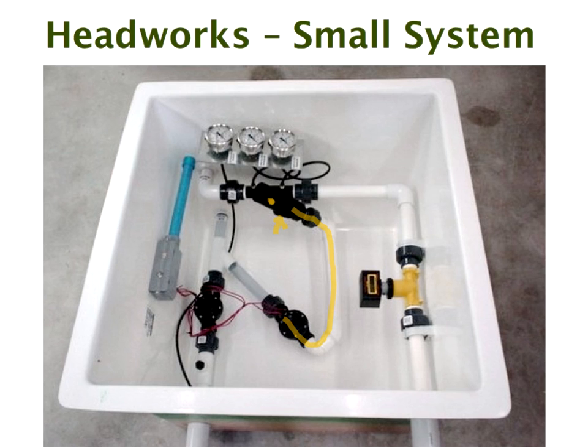Here it's got the filter flush through a solenoid valve, so you can open and close this either every cycle or every 2 or 3 cycles, so you don't get that build-up pressure difference across the screen, or you flush out the junk that I spoke about on the disc, on the outside of the disc that I spoke about earlier.